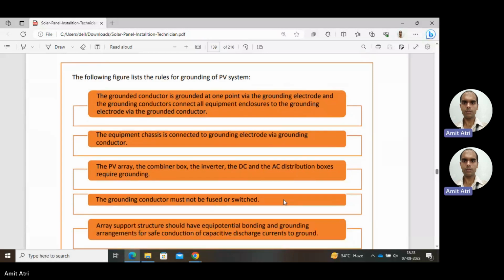Okay, means all of the components should be properly grounded, by the grounding electrode and the grounding conductors. So all of the equipment in our system should be connected to the grounding conductors. These conductors should be connected to the grounding electrode. So the next rule is the equipment chassis is connected to the grounding electrode via the grounding conductor. Along with the equipment, the chassis is also to be connected with the grounding conductor. Next rule: the PV array, combiner box, inverter, DC and AC distribution boxes, all of this equipment should be grounded. Next rule: the grounding conductor must not be fused or switched. We have to ensure that.